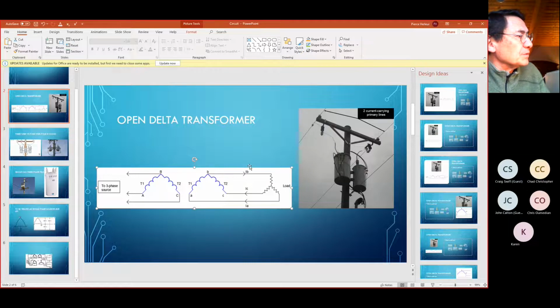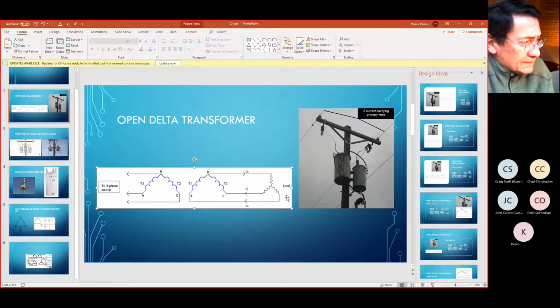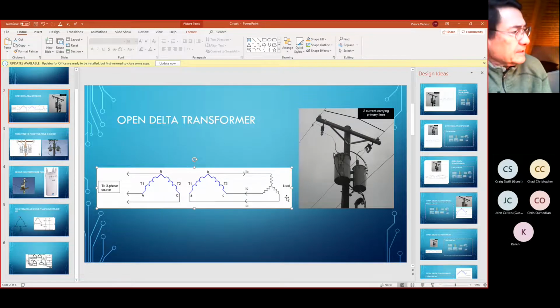In a situation like this, where there's a drive inserted right here, I hope you can see my cursor, the motor, whether it's a Y winding or delta winding motor, will not see the imbalances. That's a very important point, because the drive isolates the motor from those imbalanced characteristics, because the drive takes the 3-phase power line, creates DC, and then creates through the inverter section a balanced 3-phase AC output to the motor, at least as far as current is concerned, because the motor winding has balanced impedances. Therefore, we have a situation where in submersibles and in above ground pump motors, the motor is relieved of the effect of open delta, but the drive now becomes the sacrificial lamb.